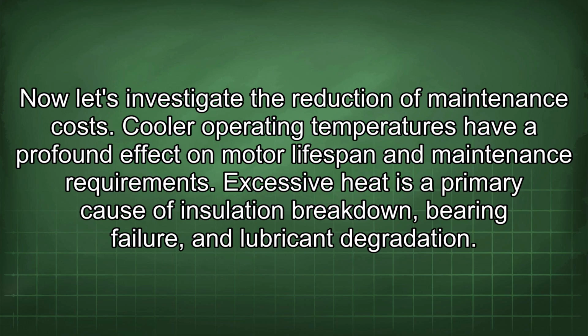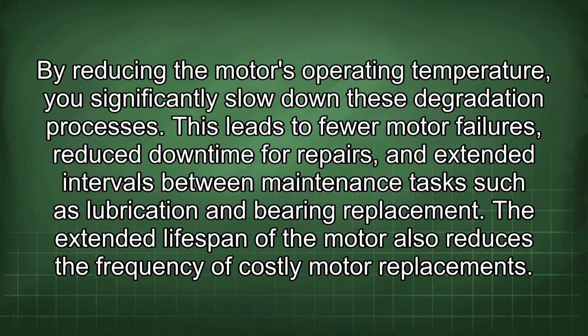Now let's investigate the reduction of maintenance costs. Cooler operating temperatures have a profound effect on motor lifespan and maintenance requirements. Excessive heat is a primary cause of insulation breakdown, bearing failure, and lubricant degradation. By reducing the motor's operating temperature, you significantly slow down these degradation processes. This leads to fewer motor failures, reduced downtime for repairs, and extended intervals between maintenance tasks such as lubrication and bearing replacement. The extended lifespan of the motor also reduces the frequency of costly motor replacement.